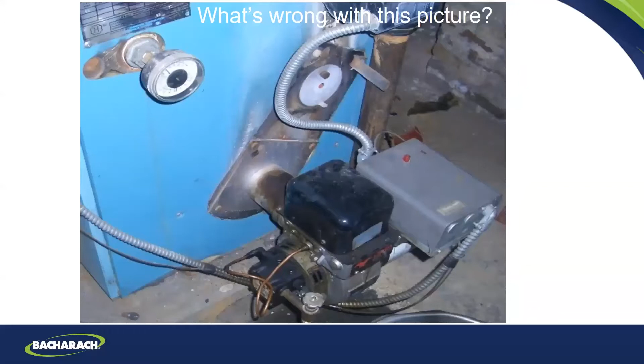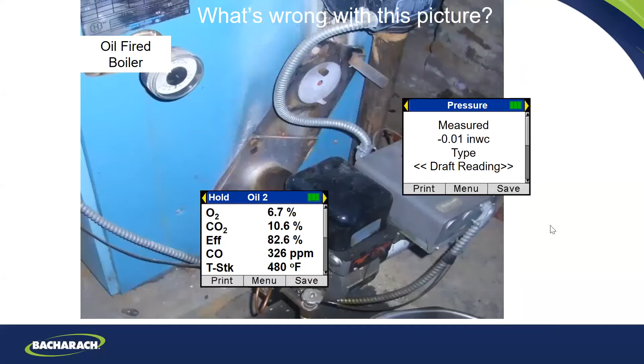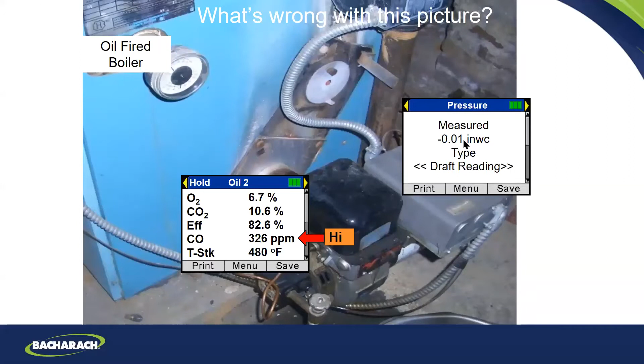So they take a draft reading, -0.01. Okay, take a combustion reading, and I know everyone's raising their hand right now saying it's too high a CO. You're absolutely right. And why is it making too high a CO? Because you only had -0.01 inches of water column in draft, okay? So it's not high enough draft. So you should have, in a furnace, -0.02 to -0.04 in a draft furnace, okay?